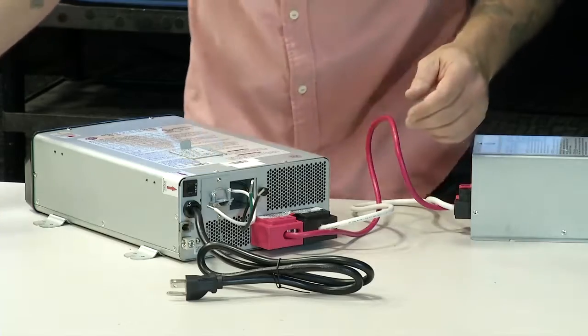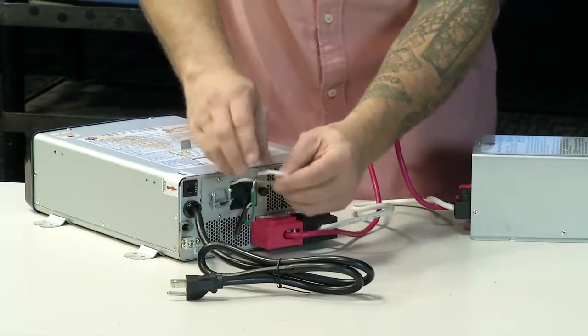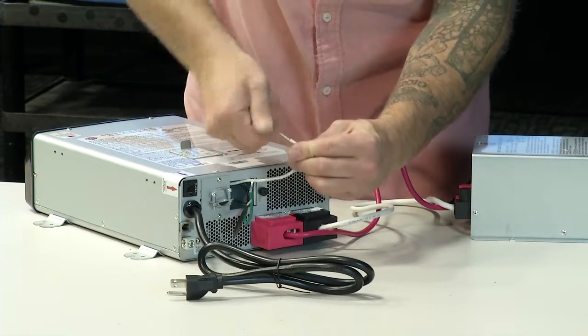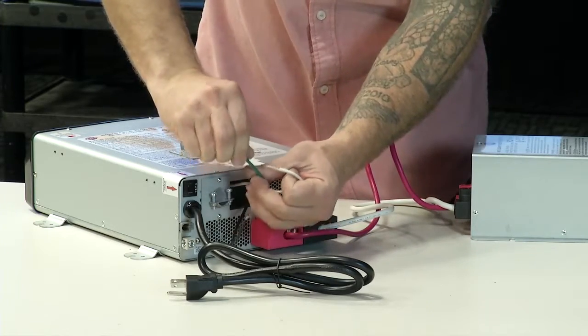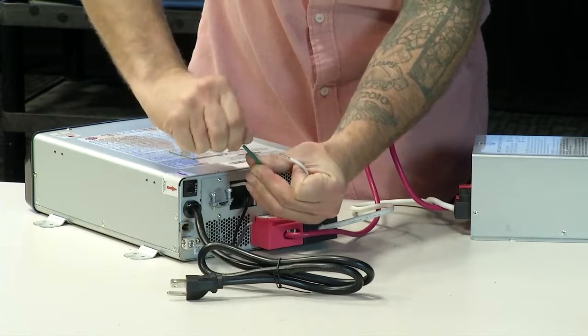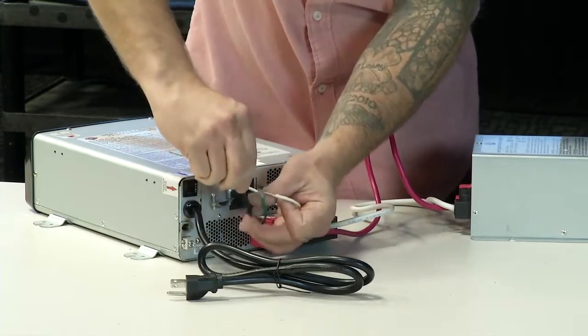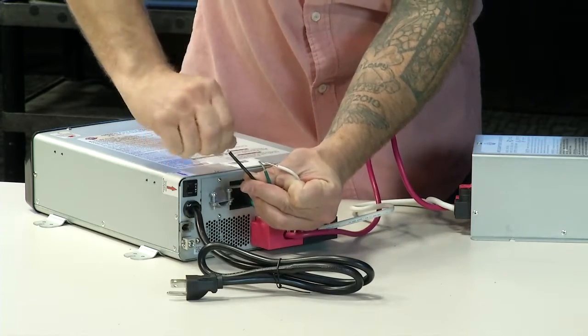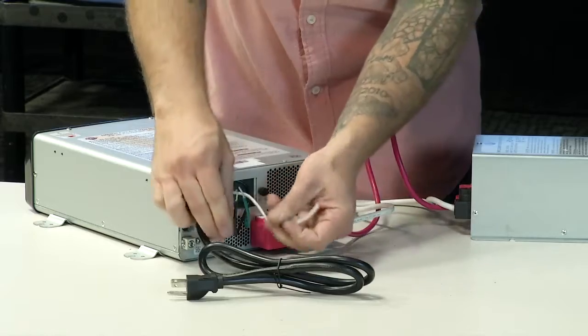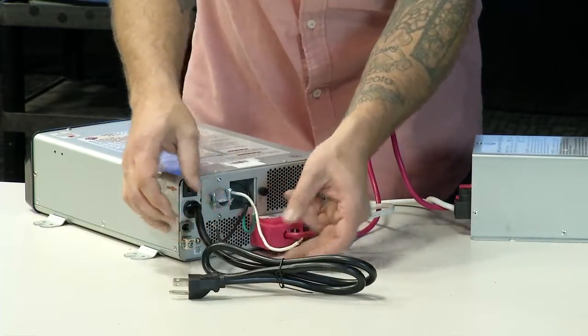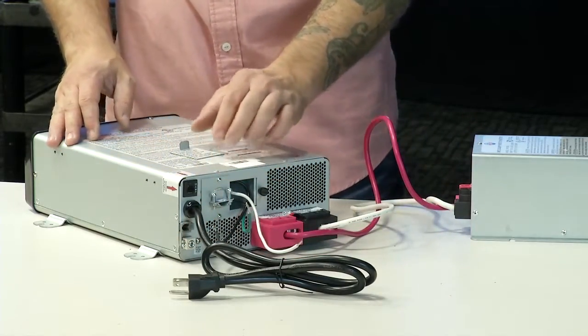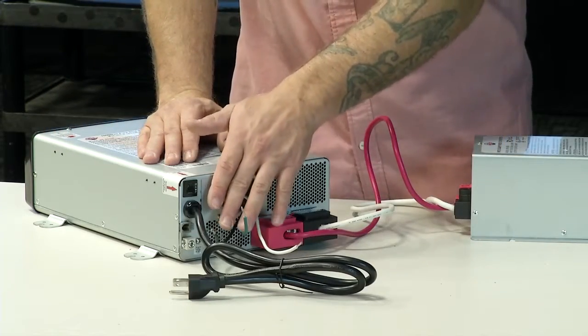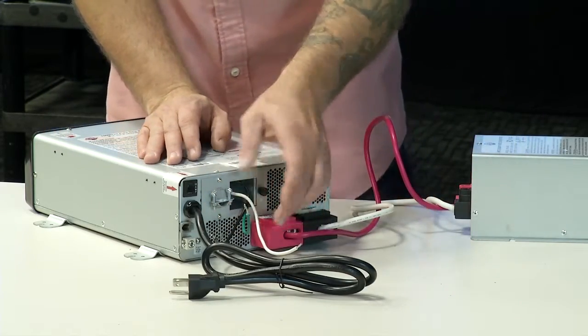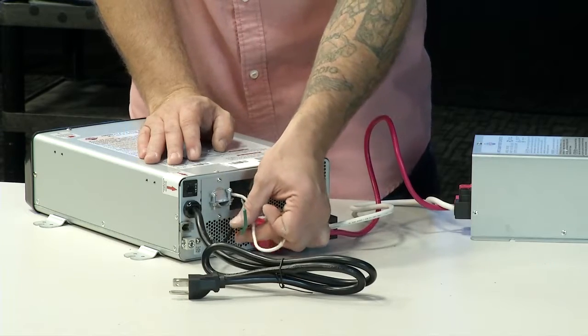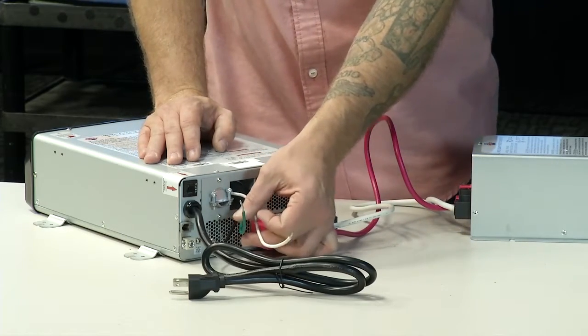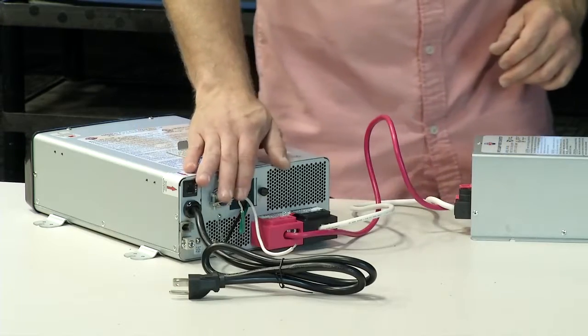So once we take the sleeves off of those, now we have some bare wire to 110 power. We want to make sure these wires don't touch. And you always want to remove your load when you're testing your inverter, because if you have a wiring problem, you need to get to the inverter wires themselves, not just the reefer wires or whatever this may be hooked up to. You always want to check the wires coming out of the inverter.